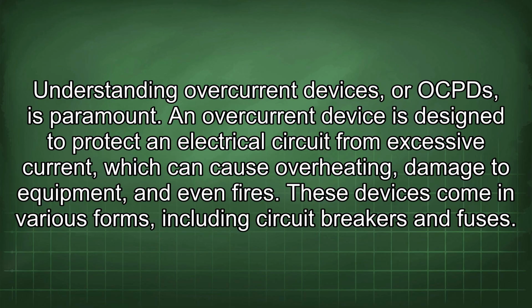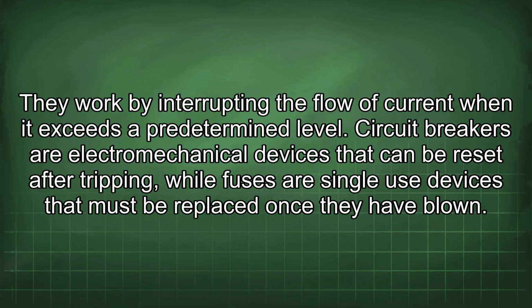Understanding overcurrent devices, or OCPDs, is paramount. An overcurrent device is designed to protect an electrical circuit from excessive current, which can cause overheating, damage to equipment, and even fires. These devices come in various forms, including circuit breakers and fuses. They work by interrupting the flow of current when it exceeds a predetermined level. Circuit breakers are electromechanical devices that can be reset after tripping, while fuses are single-use devices that must be replaced once they have blown.